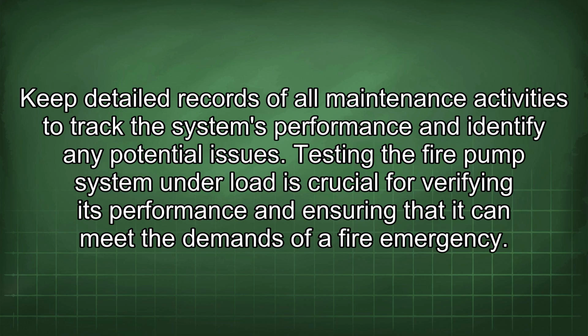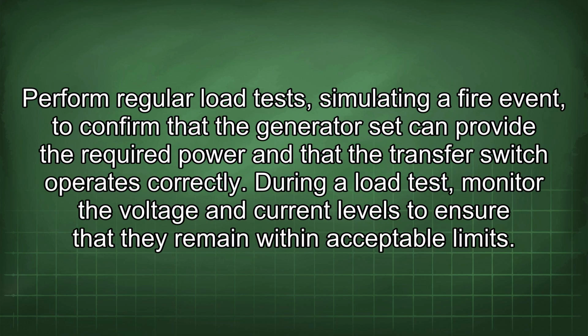Testing the fire pump system under load is crucial for verifying its performance and ensuring that it can meet the demands of a fire emergency. Perform regular load tests, simulating a fire event to confirm that the generator set can provide the required power and that the transfer switch operates correctly. During a load test, monitor the voltage and current levels to ensure that they remain within acceptable limits.